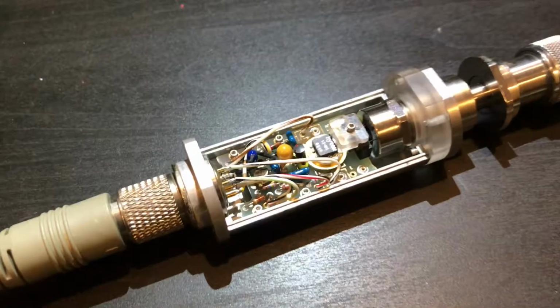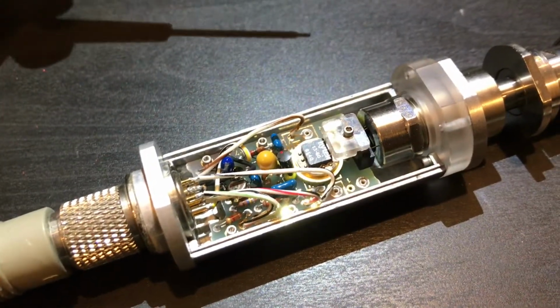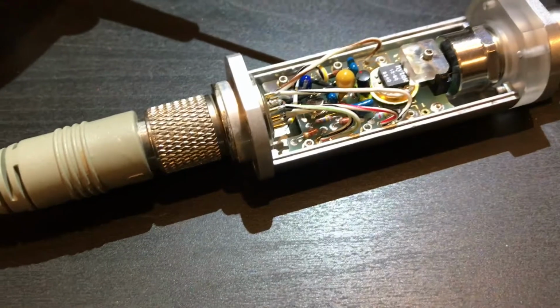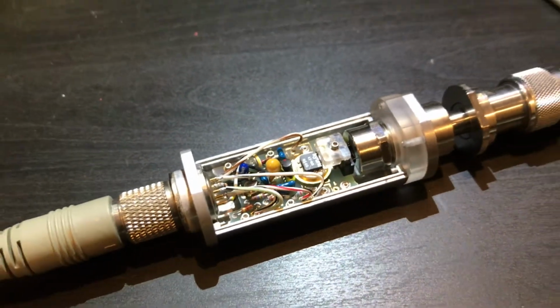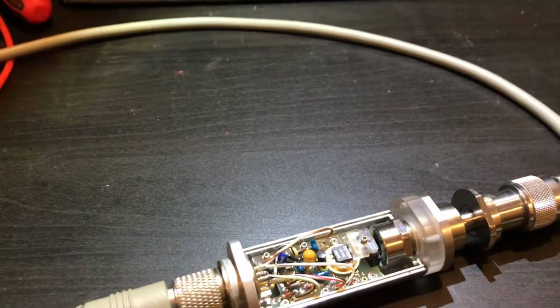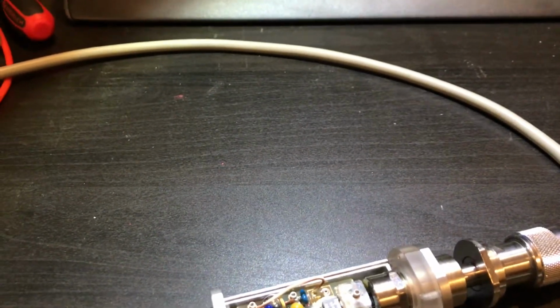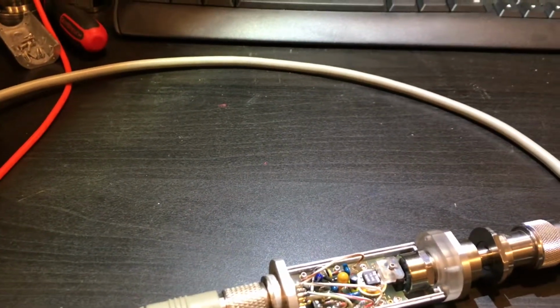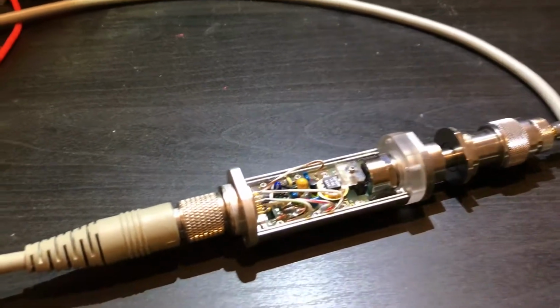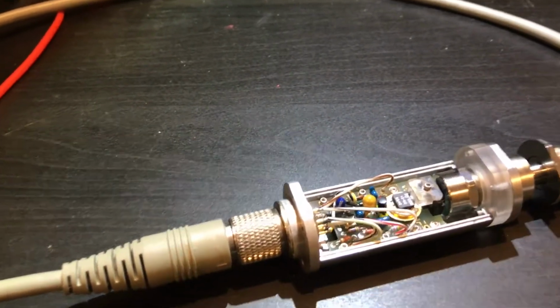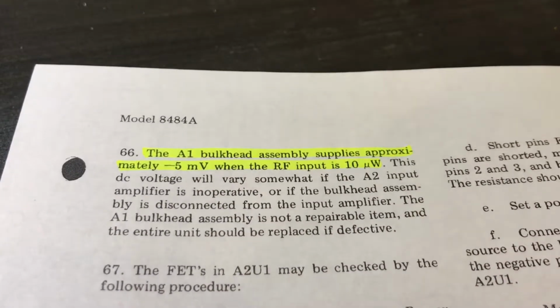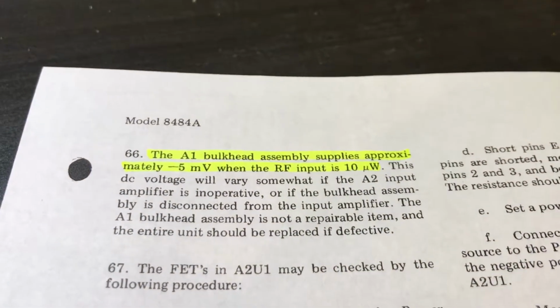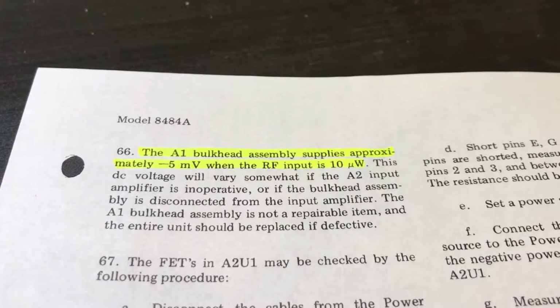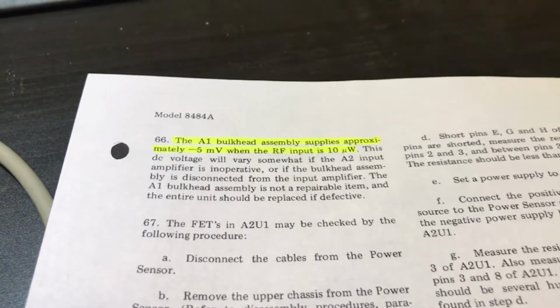And here's what I suspect is going on. The manual goes through a troubleshooting process. It's a block troubleshooting process, and it isolates a fault in the sensor to a section. Right here it talks about the A1 bulkhead assembly supplies approximately minus 5 millivolts when RF input is 10 microwatts, which would correspond to the minus 20 dBm of signal.